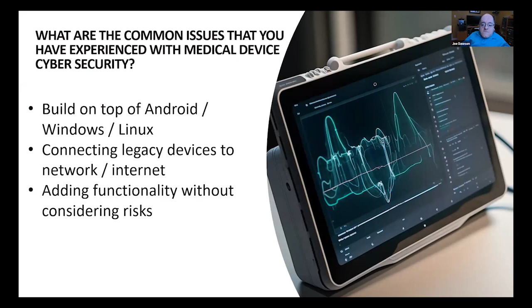Generally, the other one is just adding functionality without consideration of risk. We've seen devices which allow doctors to configure a device so that it operates a certain way, so that when the doctor goes in the operating room, he can log in, and this will set the medical device up to be configured the same way it is in every operating room where he goes. So it goes out over the cloud, grabs his configuration and throws it on the device. In some cases, when I read the risk assessments, they consider that a low-risk activity, when in actual fact it's a very high-risk activity, because if that configuration is not the way the doctor thinks it is, then perhaps when he puts his foot on a certain pedal, it will not do the behavior he expects, but something else. So having this remote configuration or ability to download configuration, just adding simple functionality that seems to be a nice-to-have, can sometimes create massive risks if you're not fully considering the impact of those changes.